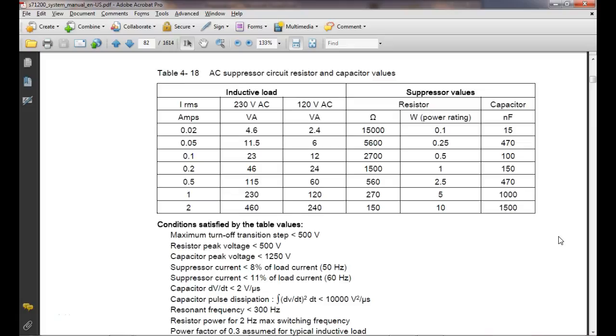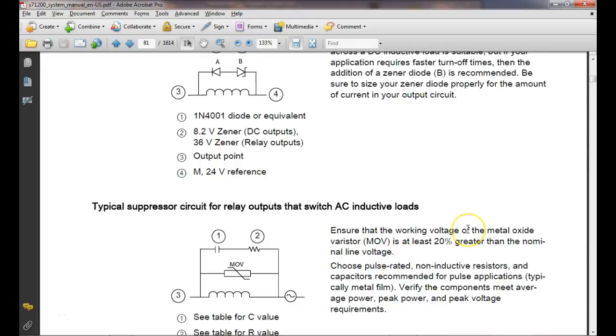What they're recommending is also to put a little RC time constant circuit in there, which we're not going to talk about. For AC, they're recommending you use the working voltage of the metal oxide at least 20% greater than the nominal line voltage. Use pulse rated non-inductive resistors and capacitors recommended for pulse applications, such as metal film, which is about all you can get now, guys.